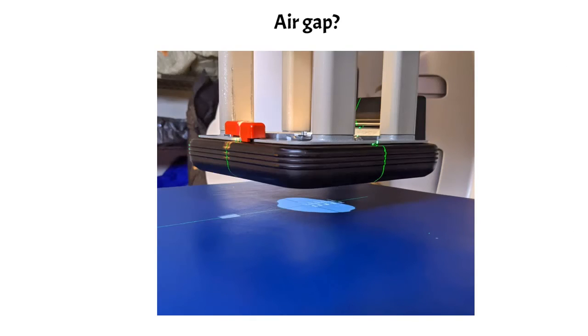which is what you see here. So this is a blue pad. In this case, it's set up to 100 centimeter SSD. And you can see that the applicator is extremely close to the skin. And this is something that we want because it helps reduce our electron penumbra and reduce scattering.